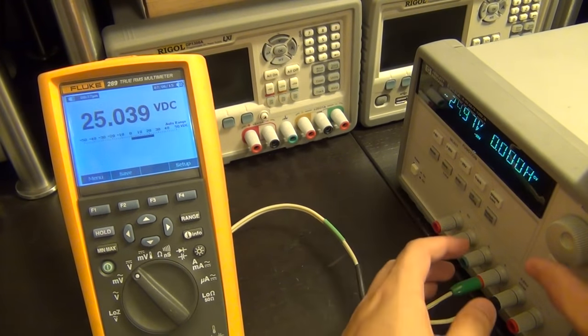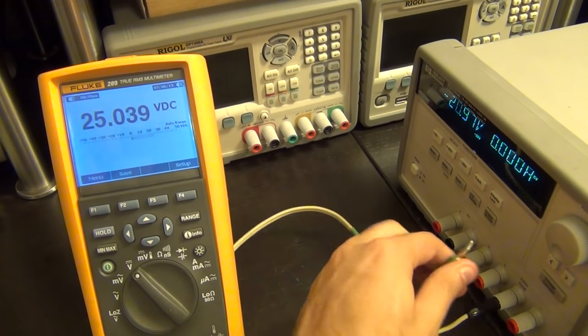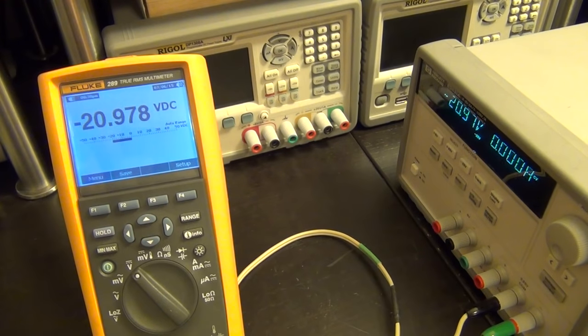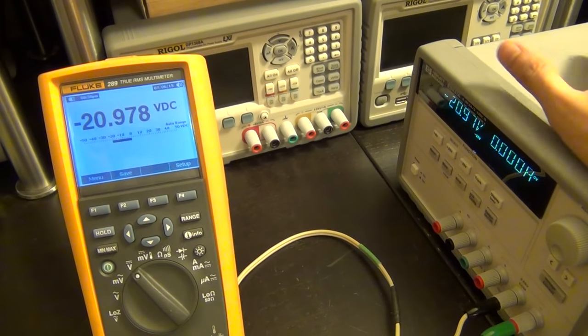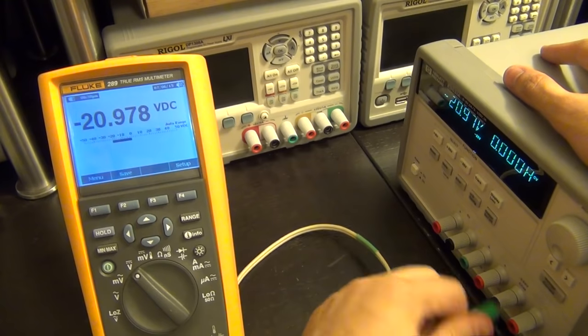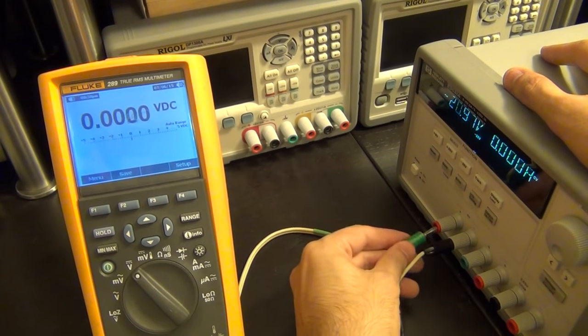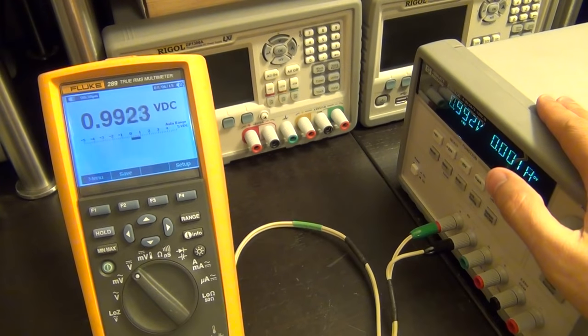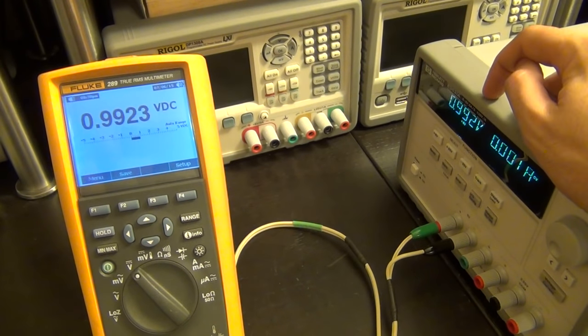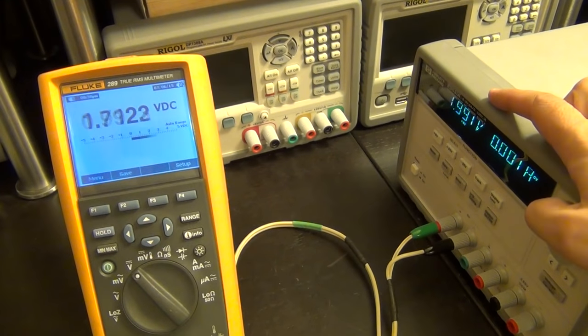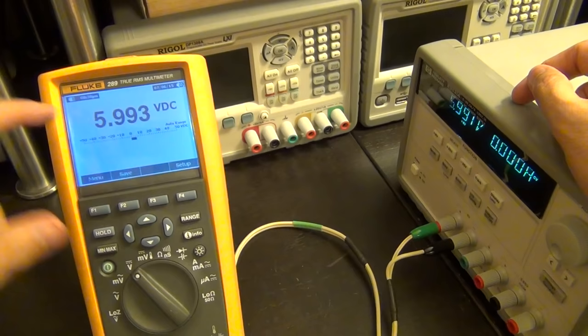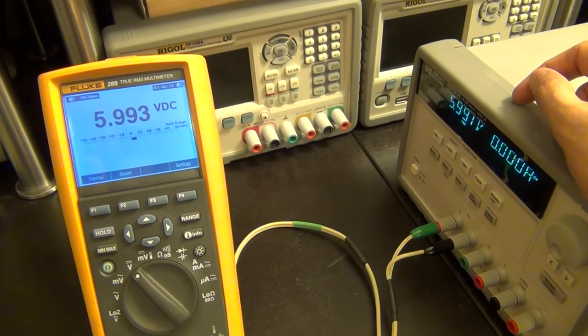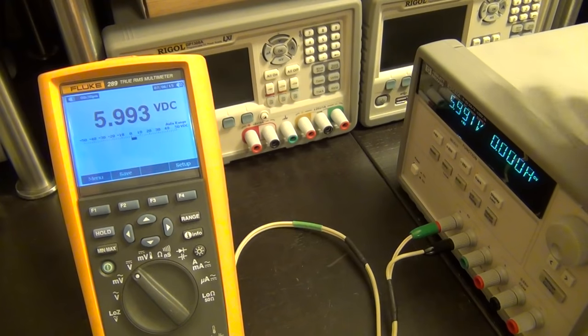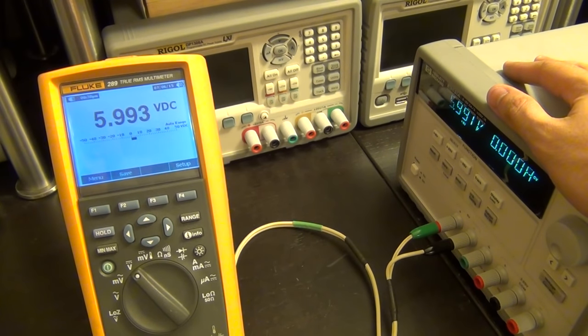And if I go to minus 25, let's set that to some random number, let's say minus 20.97, plug it in here, minus 20.97. It's very, very good, considering that it was damaged, and all the age that it has. It is very impressive. Let's go back to the 6 volt input again. Here, and let's go to 1 volt. You can see it says 0.992. 0.992. Perfect. Let's go all the way to the top. 5.991. 5.993. It's pretty good. It just needs a minor calibration to bring it up to spec completely. But other than that, it seems to be working really, really well.